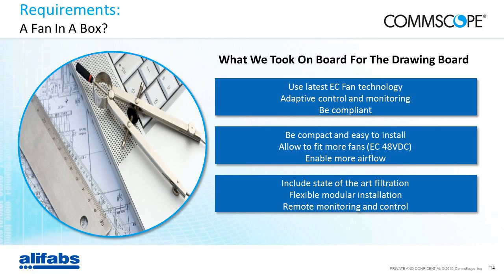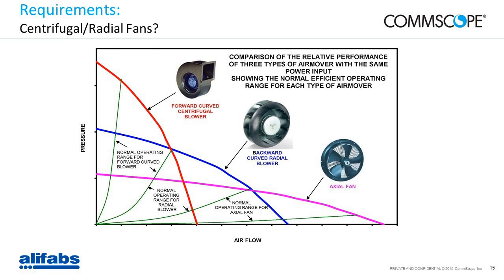I will take you through our filtration, but just going back to the basics now, I'm going to take you through all the key elements of what's in that box. The first thing is the fan. And why have we selected to use backward curved centrifugal fans? It's pretty simple, actually. We've got this pressure against airflow curve, which essentially shows how much pressure and how much restriction in the air you can fight against, and how much airflow, which means how much little delta T, and how much cooling capacity you would be able to get out of this cooling system.